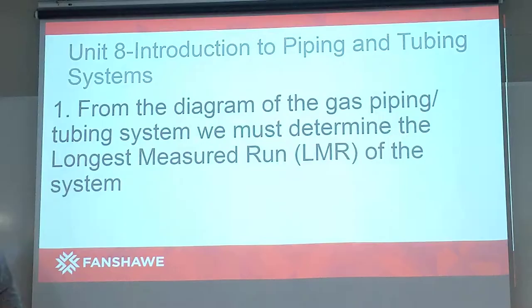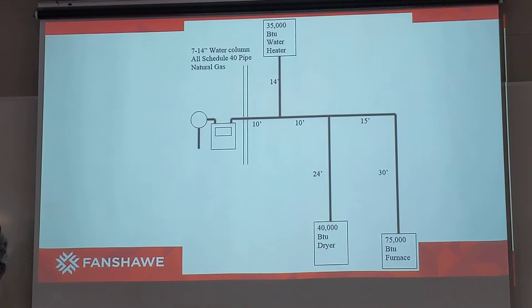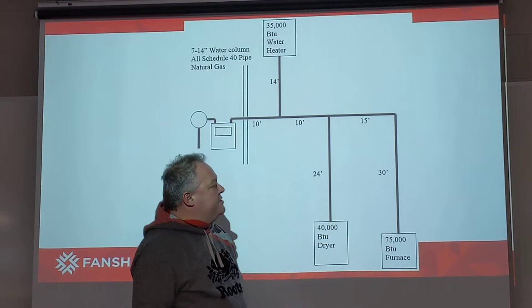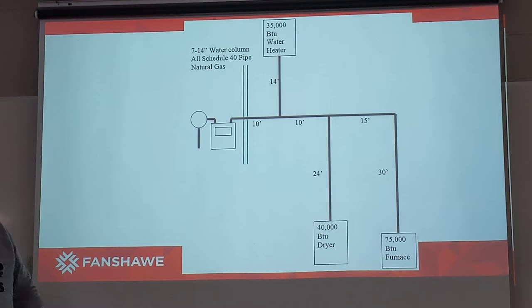Starting on a very simplified diagram, the first step we need to determine what the longest measured run, or the LMR, is in the application. Looking at the diagram, we can see we have a 75,000 BTU furnace down at the end. We have 30 feet of pipe, 15 feet of pipe, 10 feet of pipe, and 10 feet of pipe — that adds up to 65 feet. That's the longest measured run in this example.